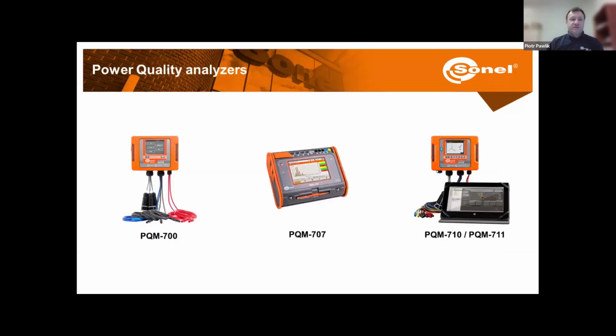And in case you are facing just some problem with a single station and you want to come, diagnose this problem and then disconnect your meter and leave, then we have portable power quality analyzers like PQM 700, which is a class S analyzer, PQM 710 or 711, which are class A analyzers. We can leave them for some time to monitor the quality of the power in the network. For example, we can leave them out for 1 week, then take them down, read recorded data from the meter and diagnose the problem. Also, we have PQM 707, which is a class S analyzer.